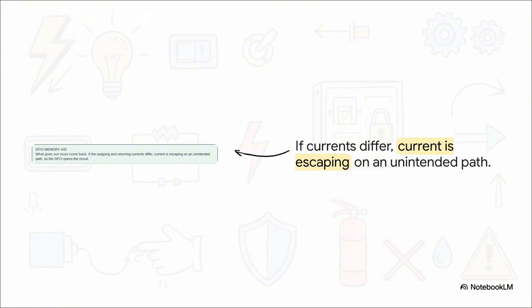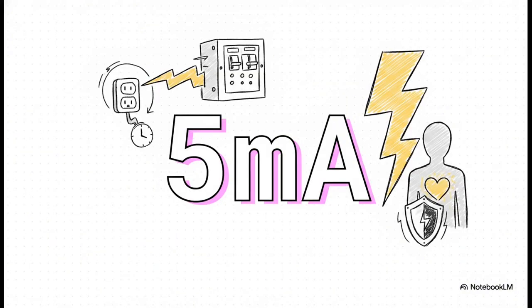In a perfectly healthy circuit, those two numbers should be exactly the same, right? But if they differ even a little, it means electricity is escaping on an unintended path. And if you're in a wet environment or working with damaged wire insulation, that unintended path could very well be through a human being to the ground. And get this, the GFCI is so incredibly sensitive, it can detect an imbalance of just 5 milliamps.